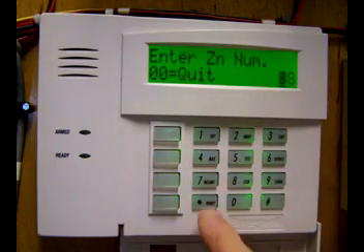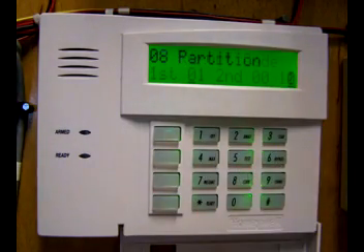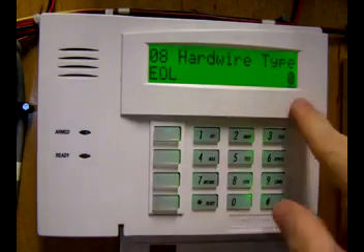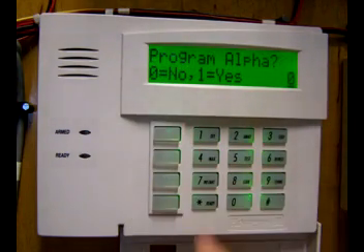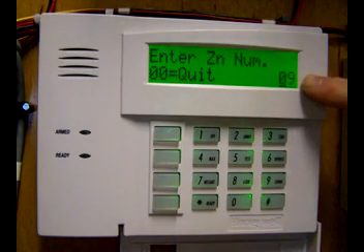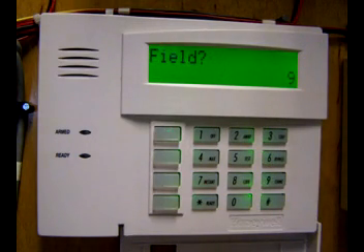Zone 8 — accept. Everything is okay except report code — accept. Perimeter is okay — accept. Partition 1 — accept. Report code: clear, 00, accept. Hardwire type is end-of-line resistor — accept. Response time: 1 — accept. New summary screen: no report codes — accept. Do not wish to alpha program — accept. Next zone available is zone 9. We do not have an expansion module so we cannot program this zone. Exit by typing 00. Then exit programming by pressing asterisk 9-9. And you're out of programming.